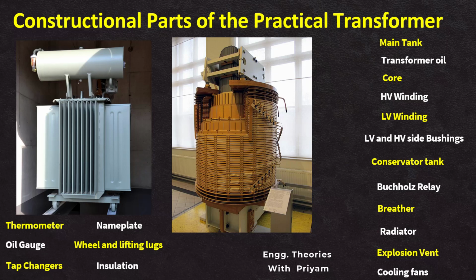The insulation in a transformer is integral to its operation and is primarily located in the core and winding assembly. Situated between the conductive components such as the core and the winding, insulation prevents electrical breakdown and ensures the effective isolation of the different voltage levels. The transformer tank also contributes to the insulation, acting as a protective enclosure. Additionally, insulating oil within the tank enhances the dielectric strength of the transformer, providing an efficient cooling medium.